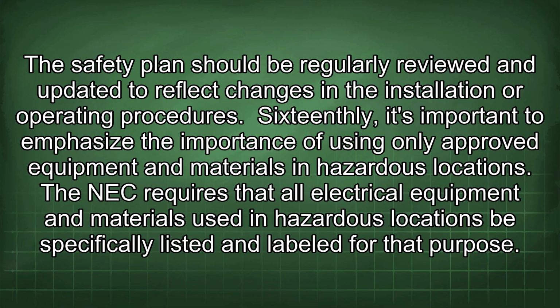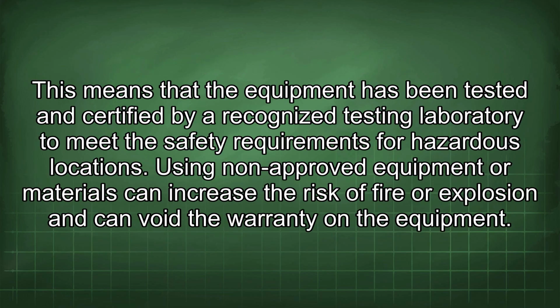procedures. 16thly, it's important to emphasize the importance of using only approved equipment and materials in hazardous locations. The NEC requires that all electrical equipment and materials used in hazardous locations be specifically listed and labeled for that purpose. This means that the equipment has been tested and certified by a recognized testing laboratory to meet the safety requirements for hazardous locations. Using non-approved equipment or materials can increase the risk of fire or explosion and can void the warranty on the equipment.